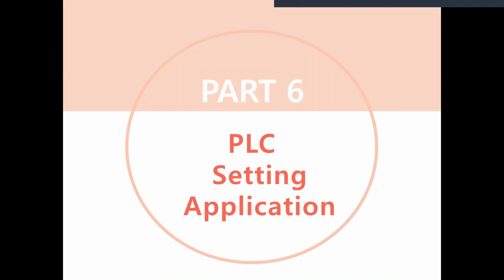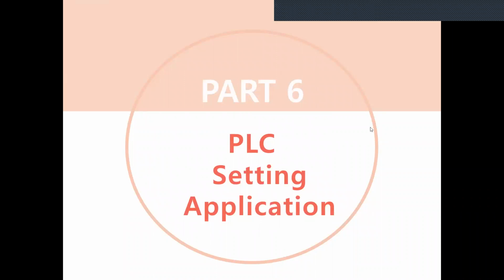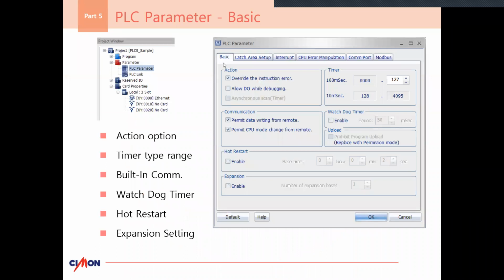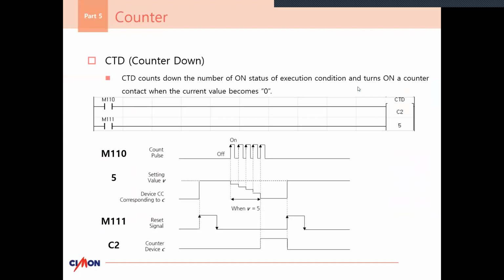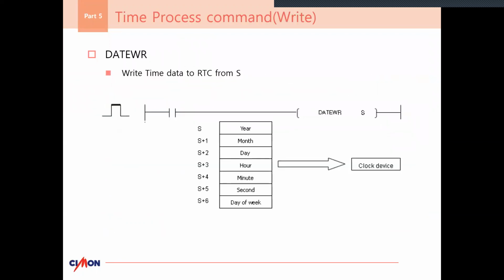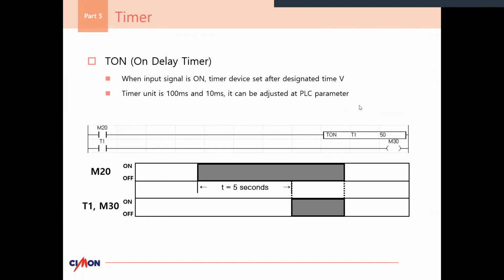Okay, I'm just going to continue. So we have the PLC setting application for part 6 to go through. Out of basics, when we go to the PLC parameter, located in your project tree, if I go down to PLC parameter and double click on the basic, I can see that's where I'm setting up my timers. T0 through T127 counts up 1 for every 100 milliseconds that goes by. So that's when I saw this operation right here. We know T1 counts 100 milliseconds per tick, so I'm taking the 100 that's embedded for T1 and multiplying it by 50, and that's my second counter. 100 times 50 is 5,000, so altogether this is a 5,000 millisecond counter, or a 5-second counter.